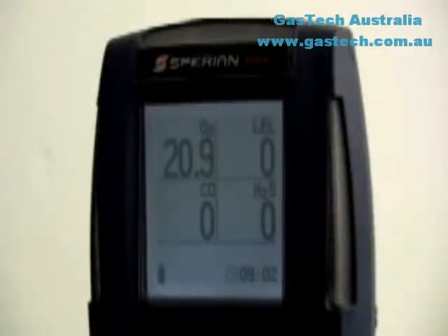Calibrating the PHD6 is a two-step procedure. Step 1 is the fresh air zero calibration adjustment. Take the instrument into an area where the air is known to be fresh.